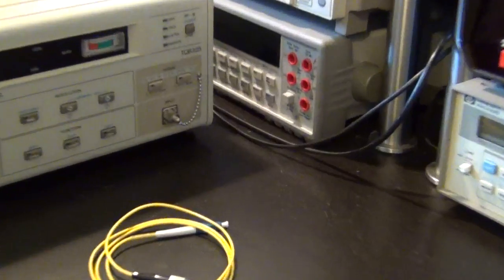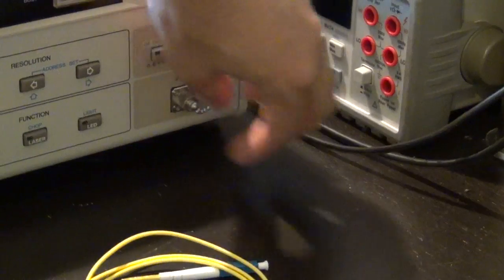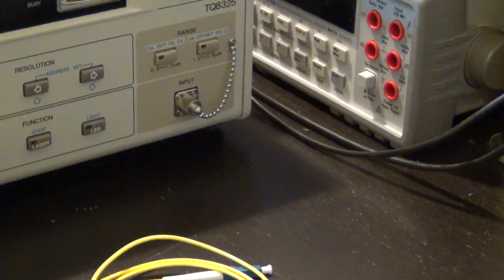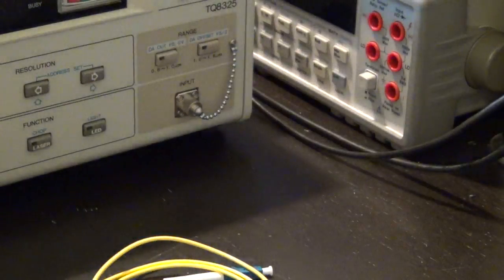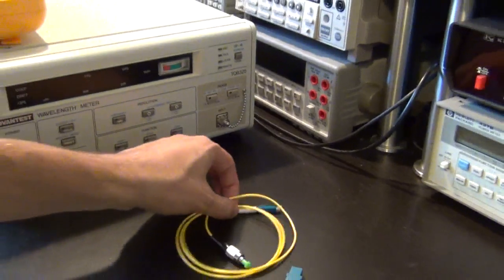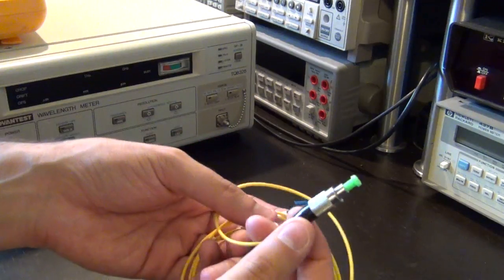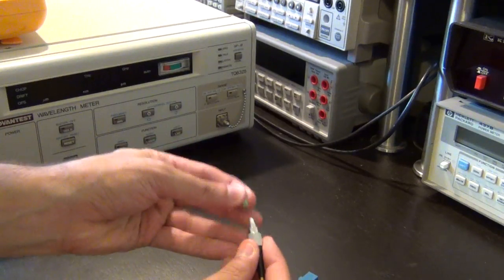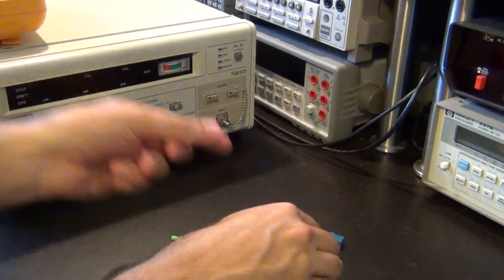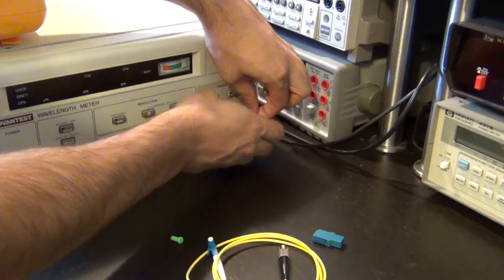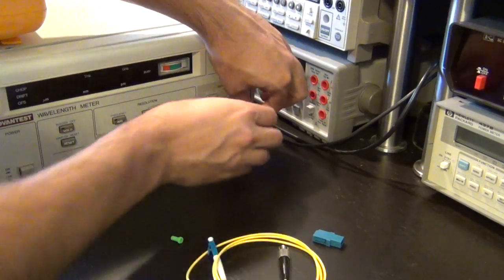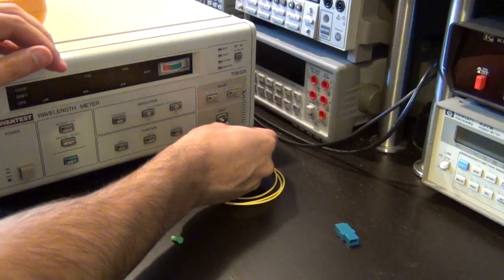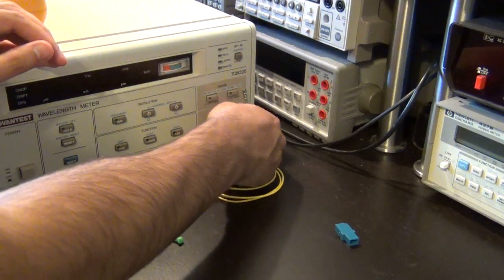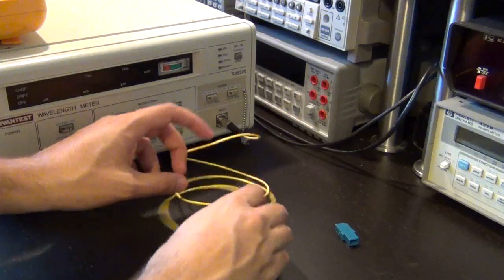Now, the instrument itself has an FC type fiber connector, which is not the same as what comes with this laser module itself. So I have a piece of fiber here, and that fiber converts from the one connector to the FC type. So I'm going to take the FC type's cap off and remove the cap from the instrument and connect this fiber to it. There we go. So now we have the same type connector on this end.